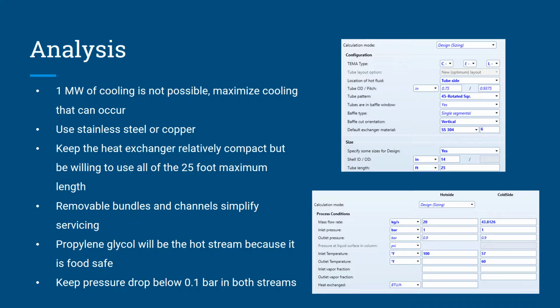It is determined from the specific heat of water, the mass flow rate of water, and the allowable temperature change that 1 megawatt of cooling is not possible for this heat exchanger. The system created maximized the amount of cooling that could occur within the parameters.